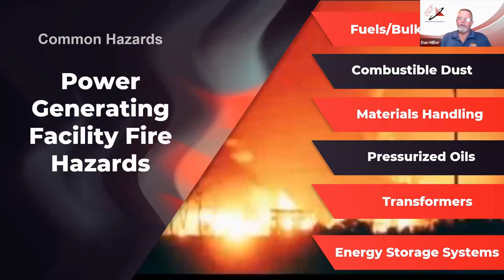Specific power generating facility hazards involve the bulk storage of different types of fuel, like coal, gases, etc. Combustible dust is always a hazard in a coal-fired power plant. Material handling, pressurized oils—specifically in the under-turbine lube oil system—and transformers, which are filled with combustible oil and contain high energy. Energy storage systems contain many hundreds, if not thousands, of lithium-ion batteries, and that is becoming a more preeminent problem.